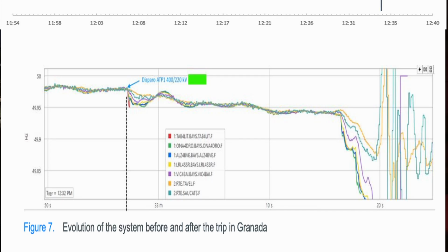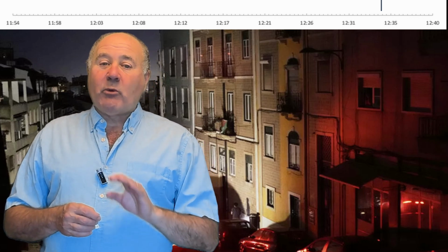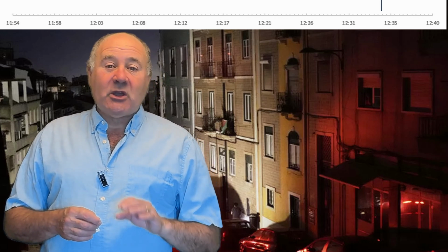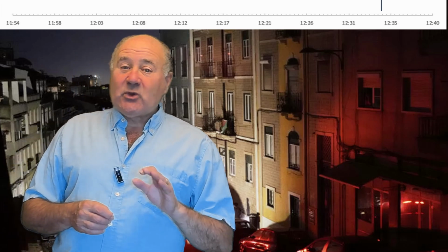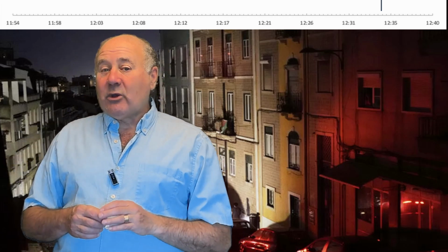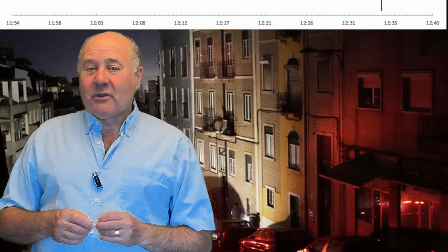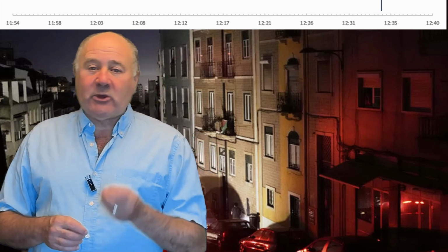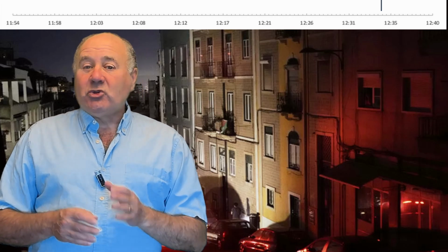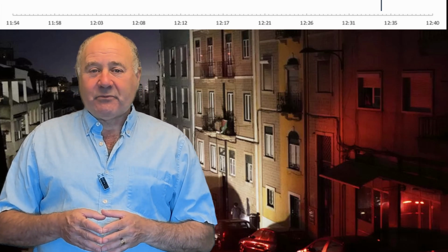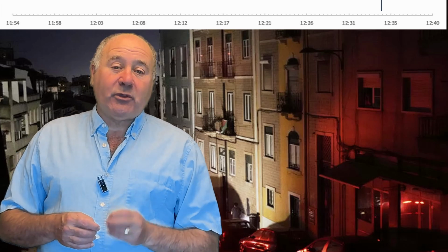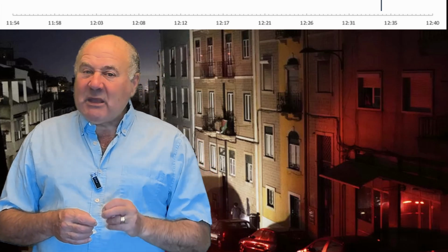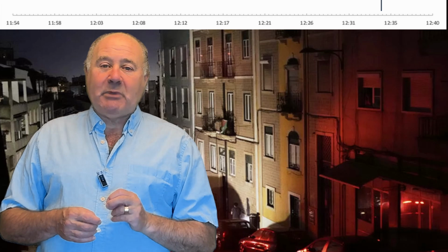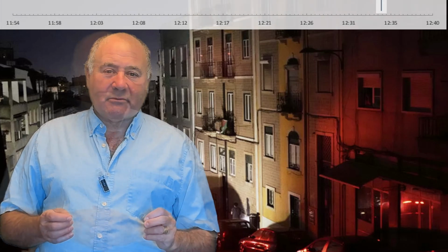At 12:33:19 and 620 milliseconds, Spain was importing 4.6 gigawatts of power from France through the AC network. This transmission line was tripped to avoid bringing down the French grid as well. The transmission line from Spain to Morocco also transitioned from exporting to importing and then tripping due to under-frequency protections. At 12:33 and 24 seconds, about a minute after the first trip, the Iberian Peninsula is dark.